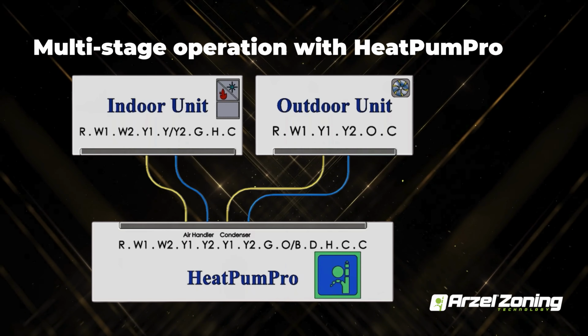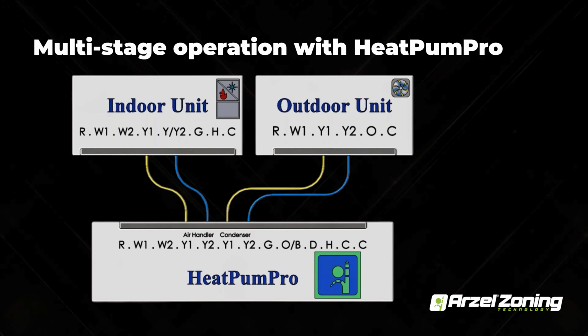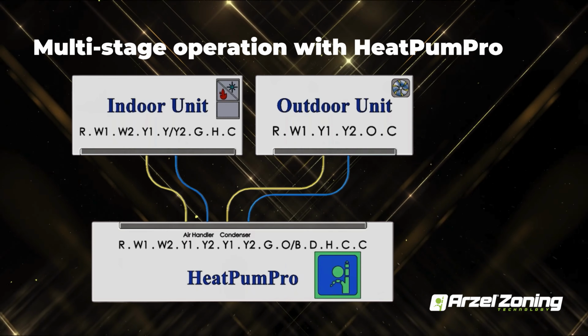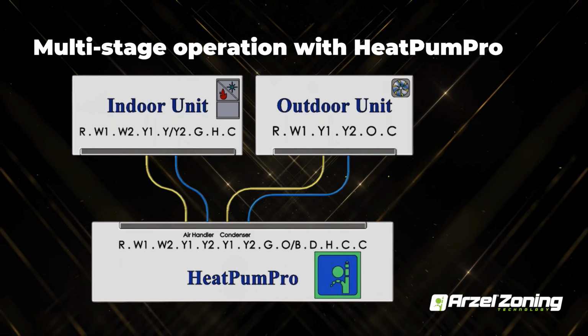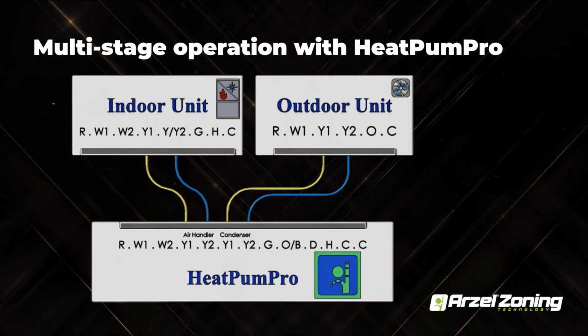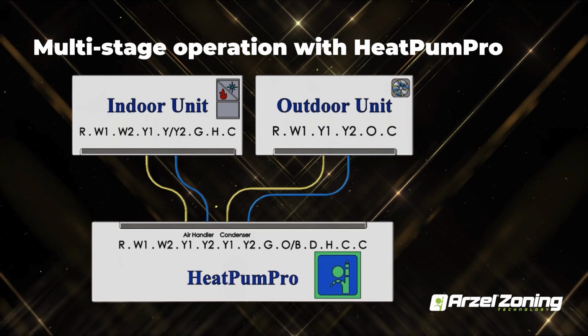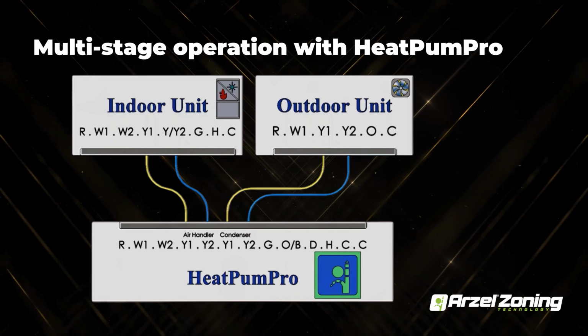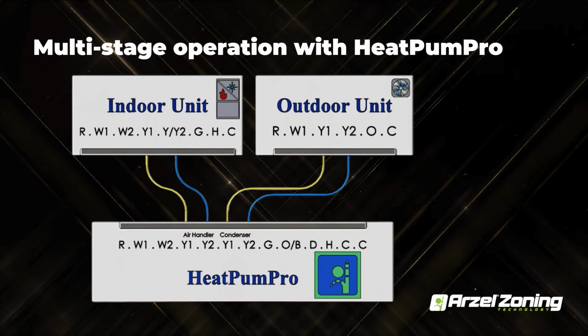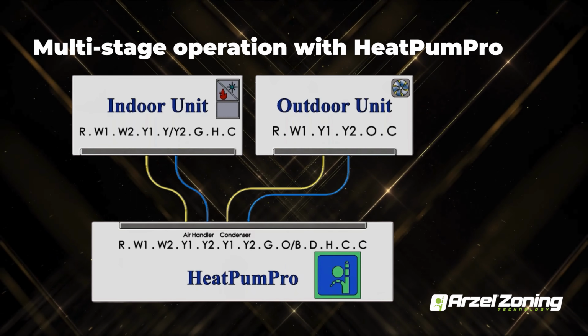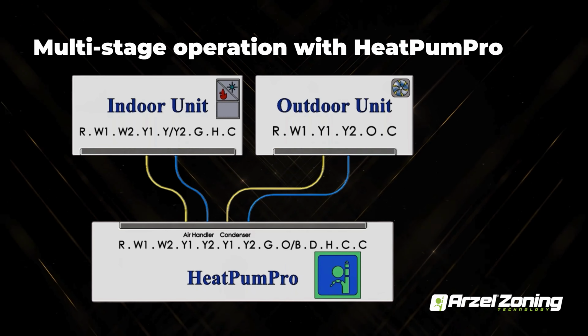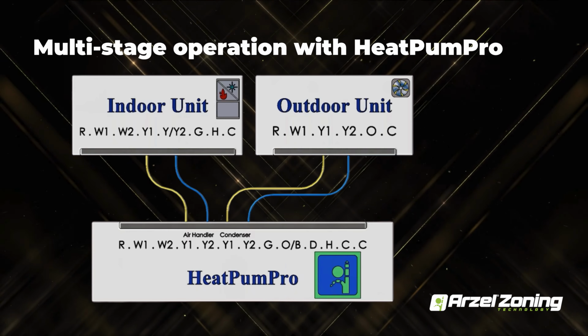So there's two settings in the HeatPumPro. One's a heat stage threshold. The other is a cool stage threshold. Those are the temperatures that you're looking to maintain in the ductwork before we upstage the outdoor unit. So if after 3 minutes you're not able to hit that heat or cool stage threshold, the panel will upstage to second stage and kick on your condenser to second stage output. And then the indoor unit is all based on zone weighting.